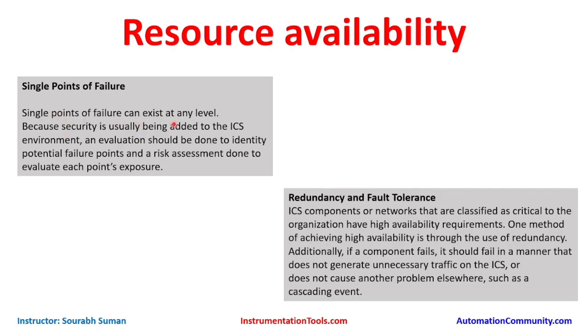Single point failures can exist at any level of your control system. Since security is usually being added to the ICS environment, an evaluation should be done to identify potential failure points, or a risk assessment should be done to evaluate each point's exposure. For example, if a server has only a single power supply, that is a single point of failure. Similarly, if a network has only a single link connecting all controllers, CPUs, processors, HMIs, and field controllers, and that link goes down, your complete communication will be cut off.